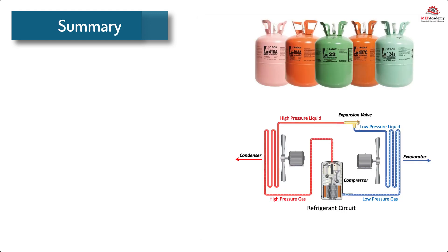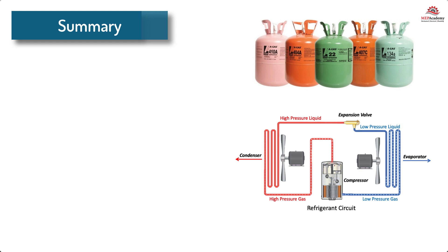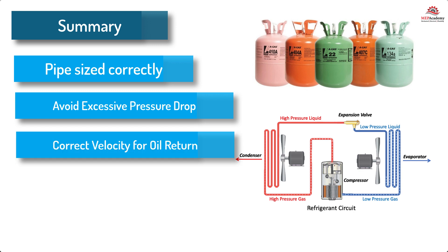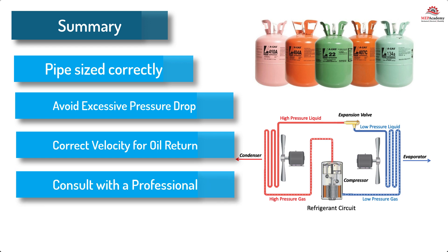Summary. Overall, the design of the refrigerant piping system should be carefully considered to ensure that the system operates efficiently and reliably. A well-designed system will ensure that the suction, liquid, and discharge piping is large enough to prevent excessive pressure drop, yet small enough to ensure that the velocity will carry the oil back to the compressor crankcase. It's recommended to consult with a professional HVAC engineer to ensure proper design and installation.